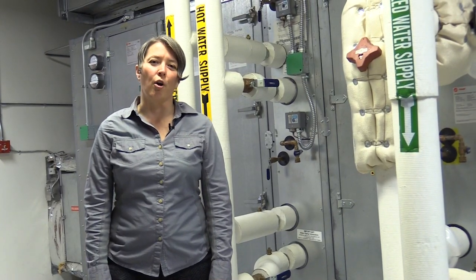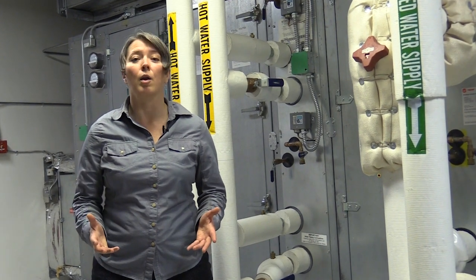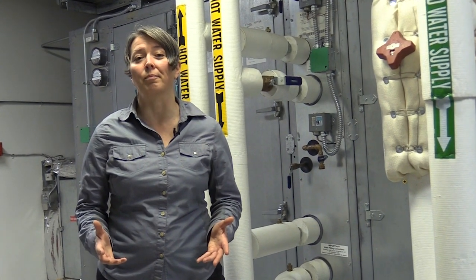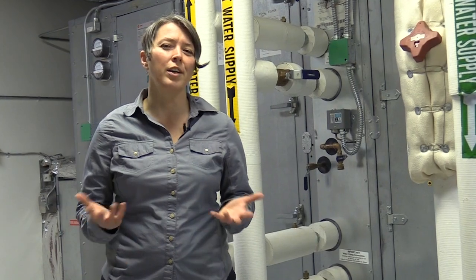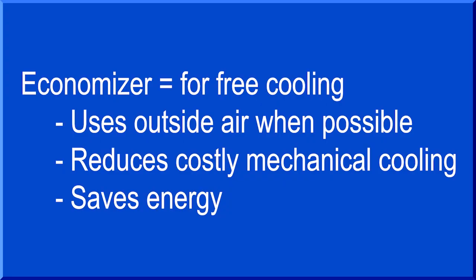So in this video, we'll use data loggers to verify that economizer controls are working properly. So what is an economizer? Well, an economizer is a control strategy that essentially means free cooling by using outside air. This minimizes the costly mechanical cooling when conditions permit. And it's a great energy saving strategy.